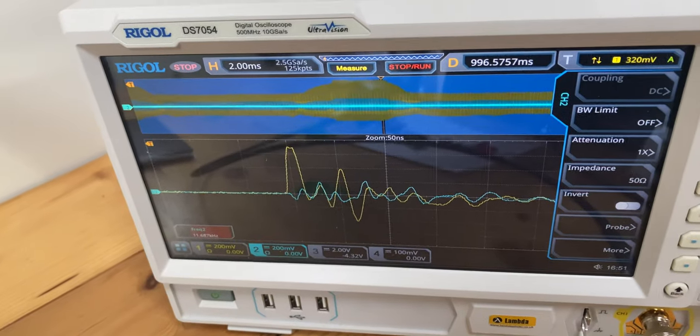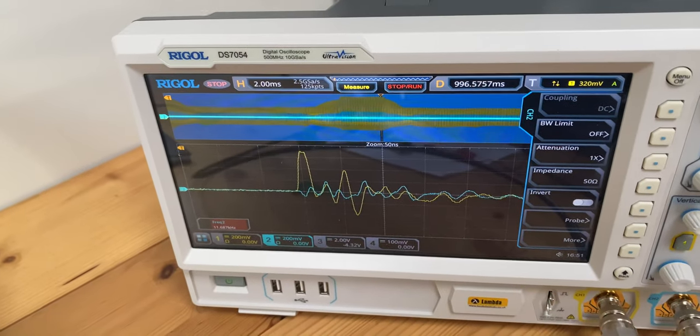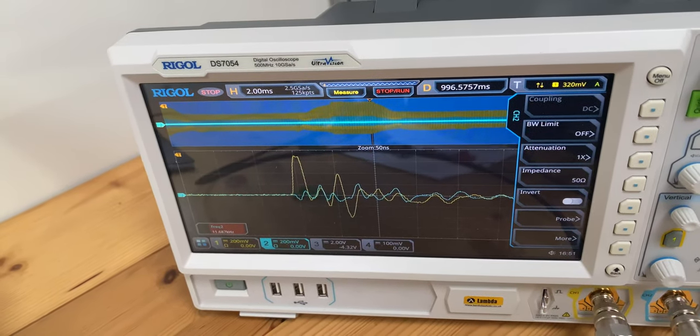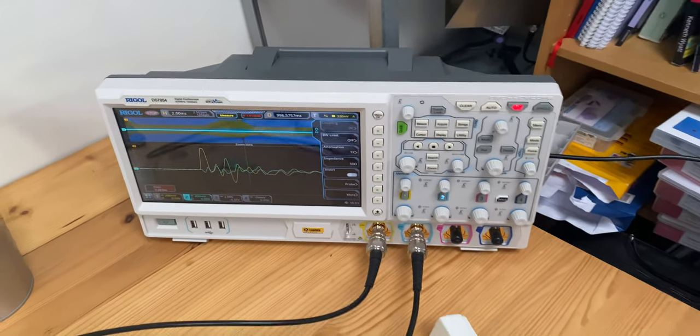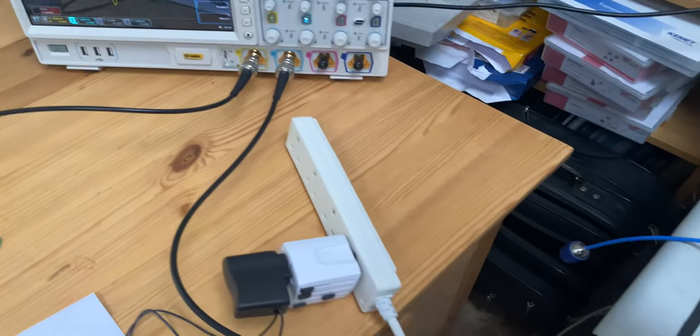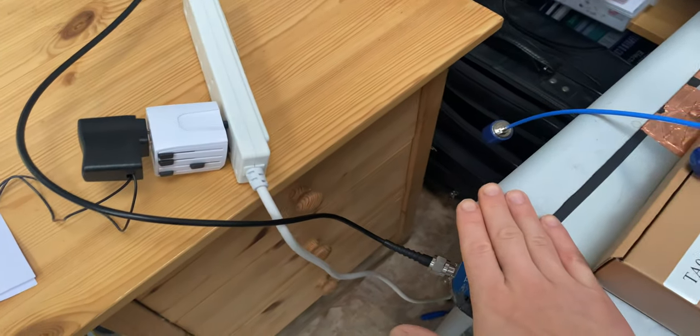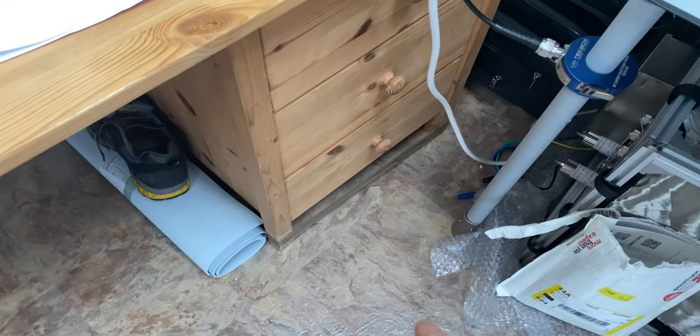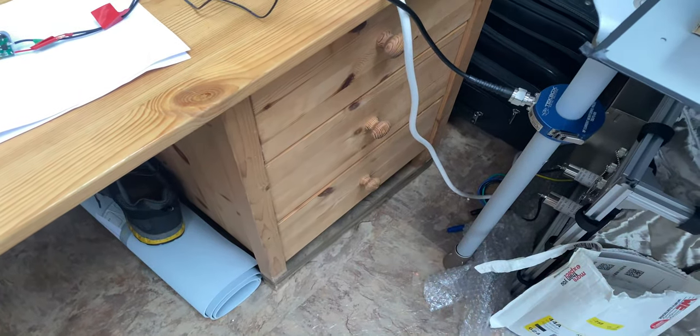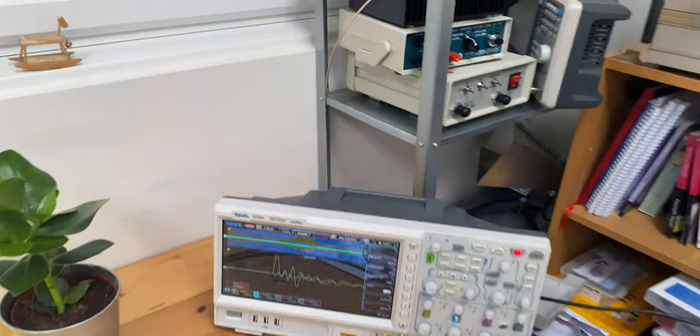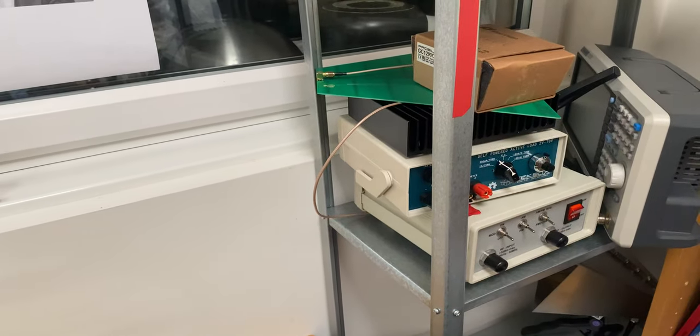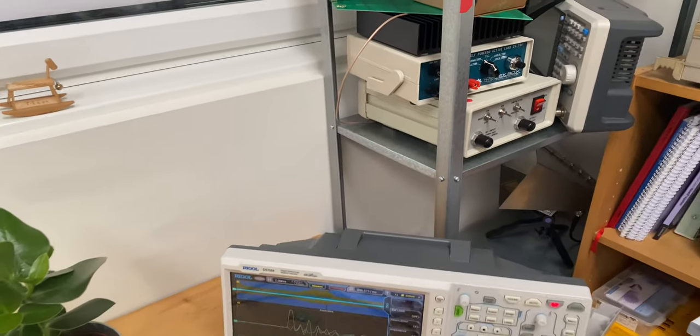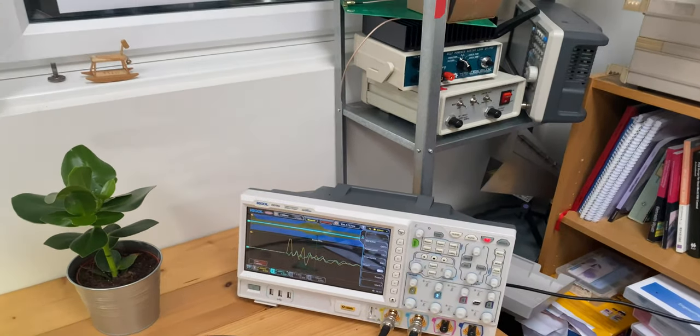And this is a good demonstration to show that when the common mode current travels, they use any possible metal structure that they can find. So in this case, they find the metal structure of the table. They find the earth, of course, as a part of the transmission line. And I'm pretty sure if I clamped on this, I will also be able to measure some common mode current on this post here.